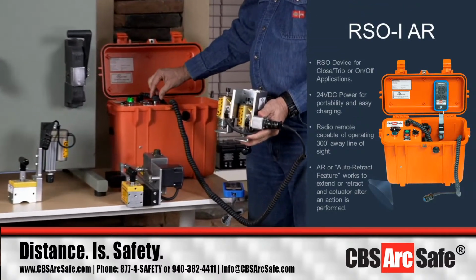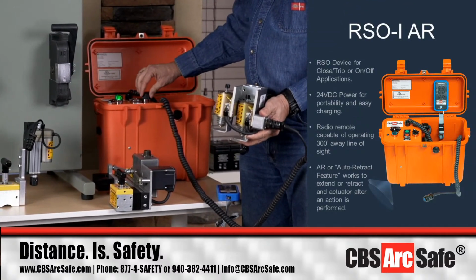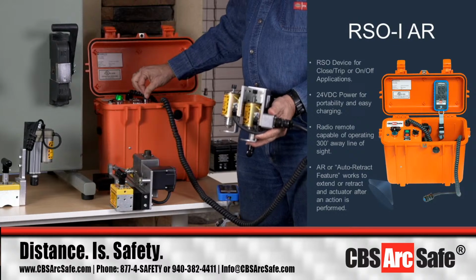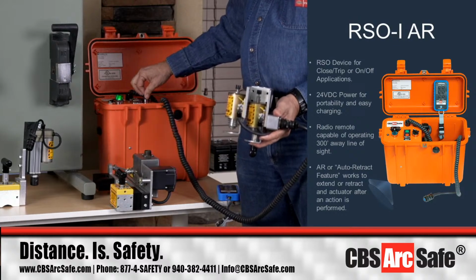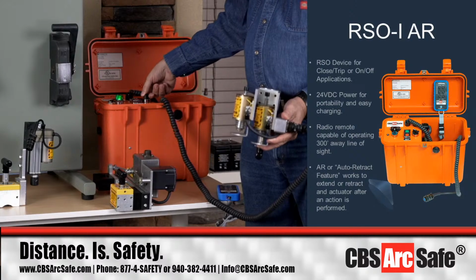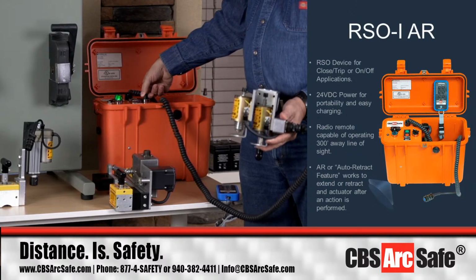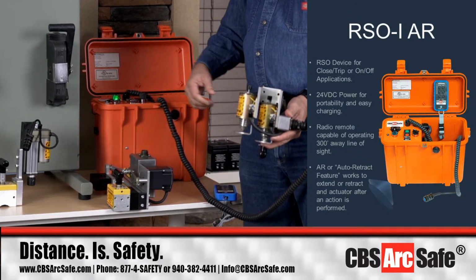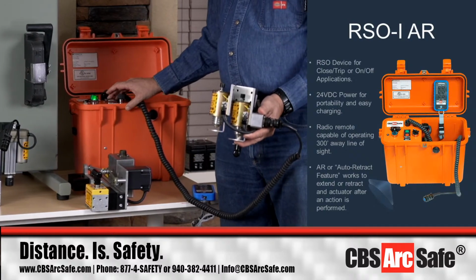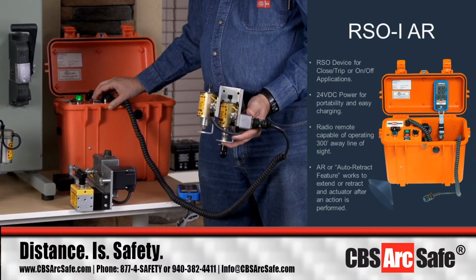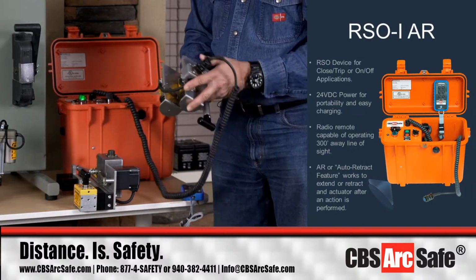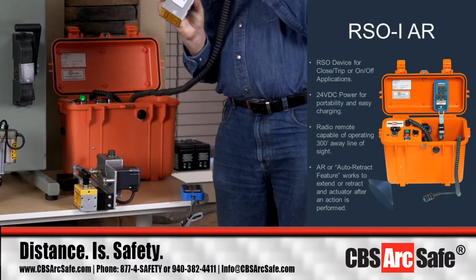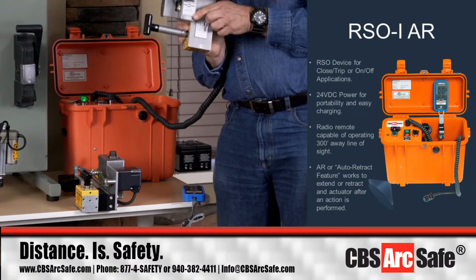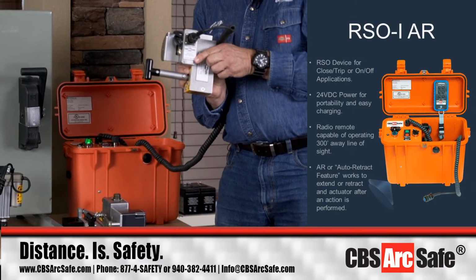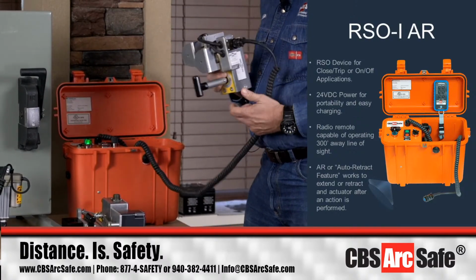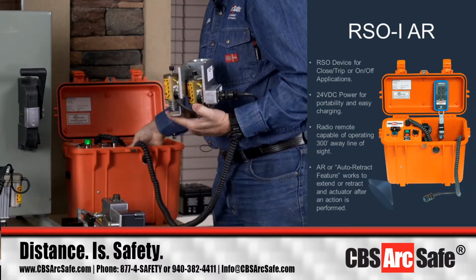I haven't touched any of the operating buttons to trip or close, but if I flip AR, suddenly the close solenoid actuates by itself. We don't want that to happen when you go to put this on a breaker. So always check to make sure it's operating in the proper position. If you notice the fine print on the side of the actuator, it says do not use AR.